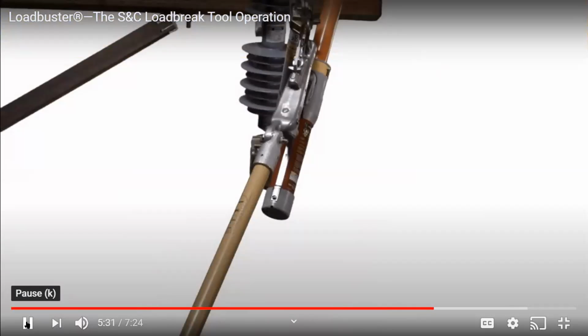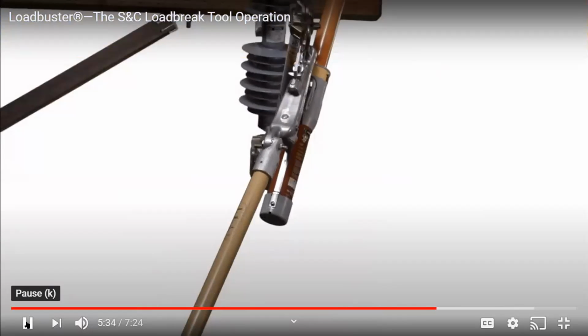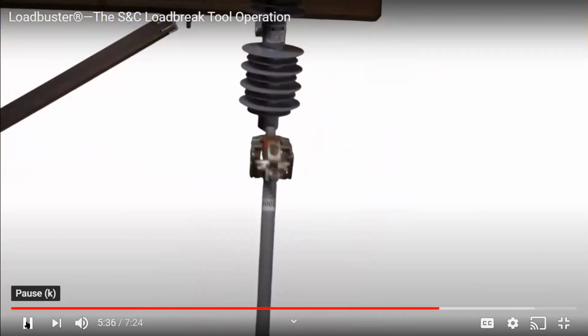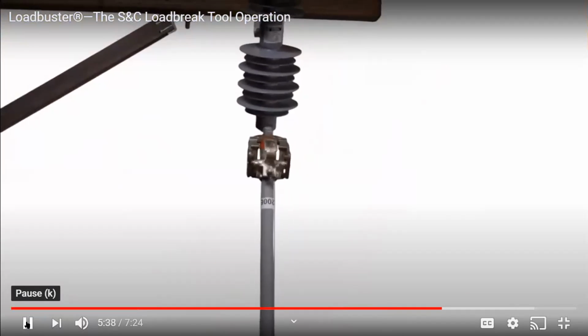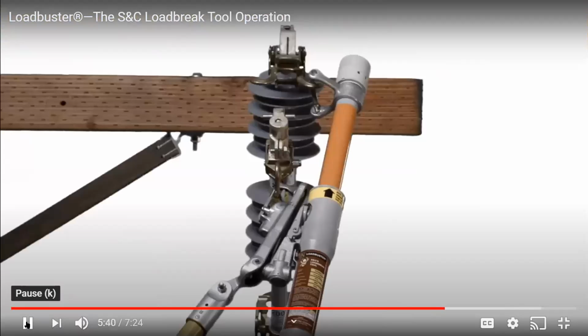Remove the loadbuster tool from the pull ring by turning the pole. This will deflect the pull ring latch to release the pull ring. On devices where the fuse will drop fully open by gravity, it may be preferred to remove the loadbuster tool by rolling it off, both the attachment hook and pull ring, at the same time, merely by twisting the pole after the loadbuster tool has been tripped and fully extended.